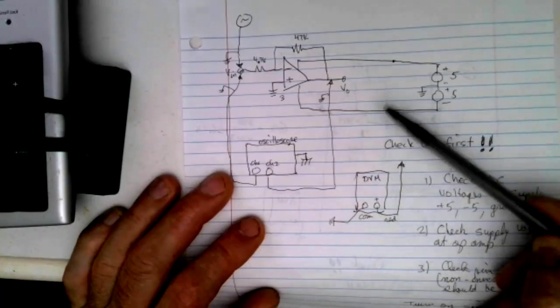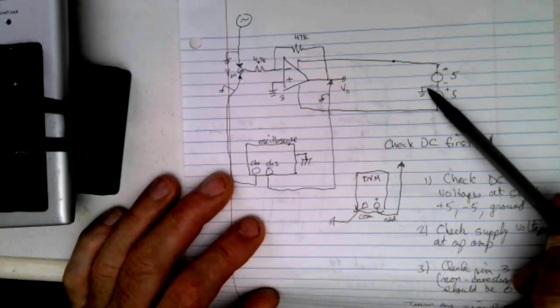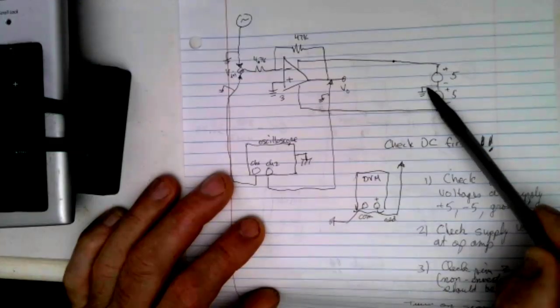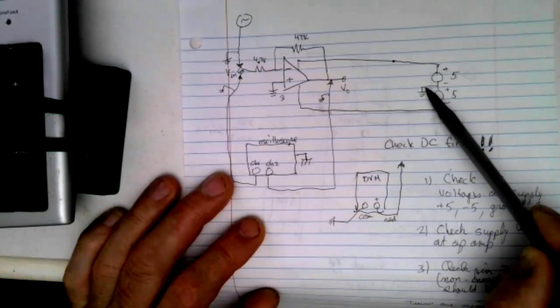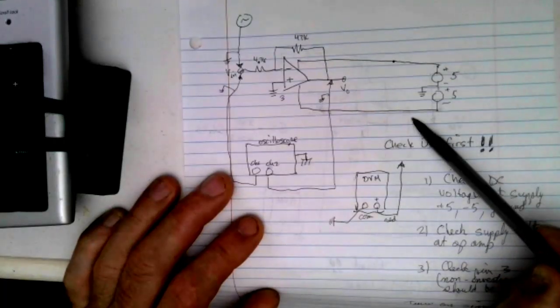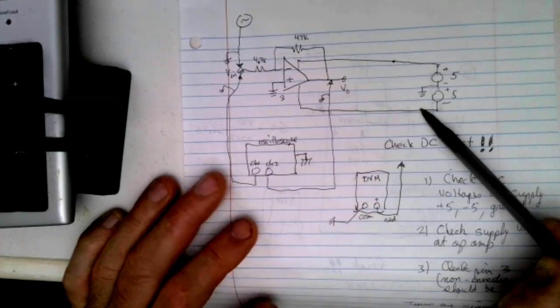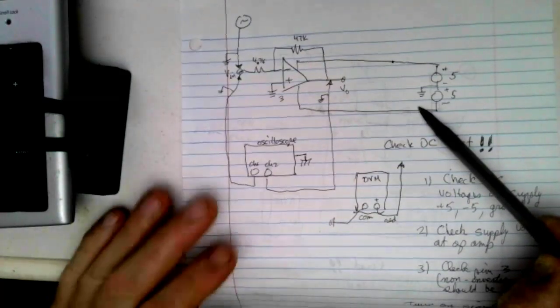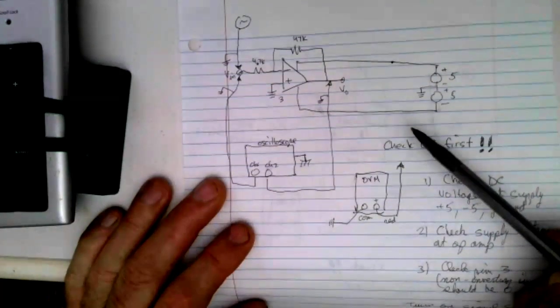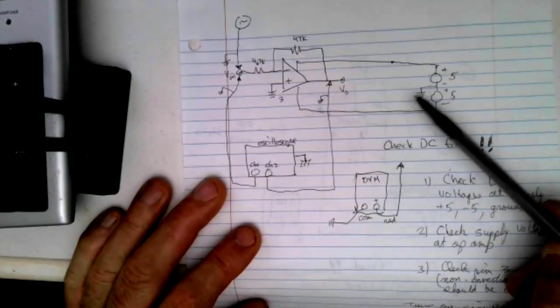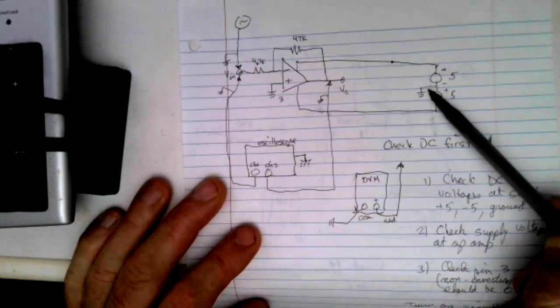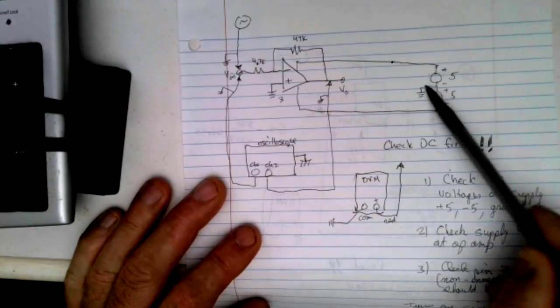Now, if this potential is not 0, that means you didn't connect this up to your circuit ground. That's a common thing that happens. That's why you check right at the supply - if the supply voltages aren't right at the supply, they're not going to be right anywhere else. So if you find that this voltage is not 0, fix that.